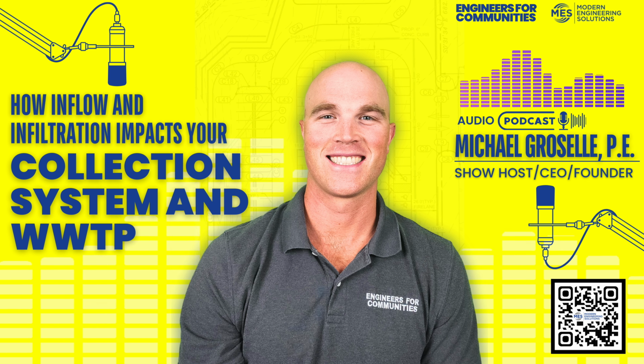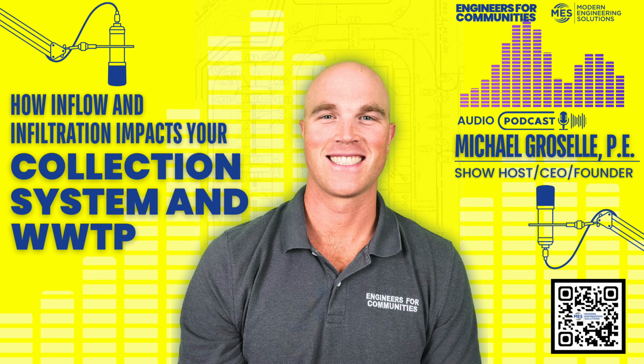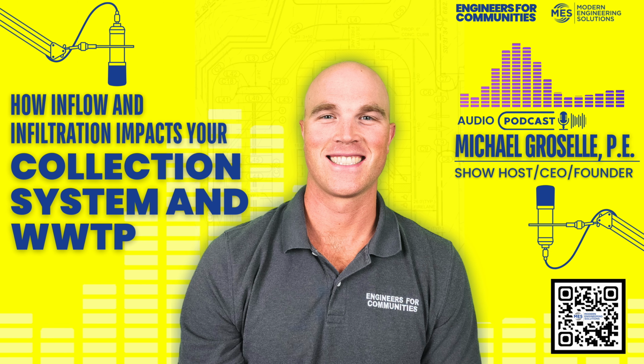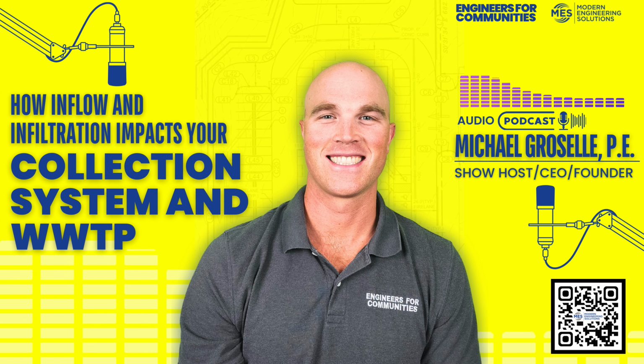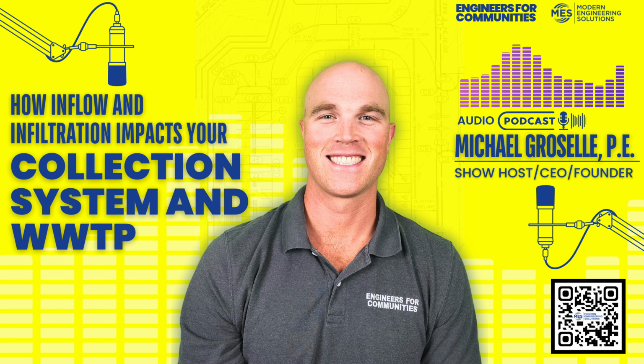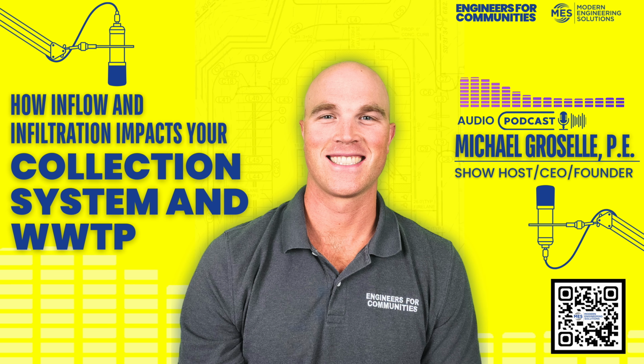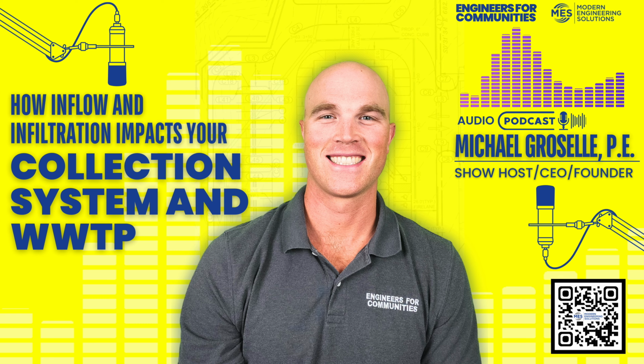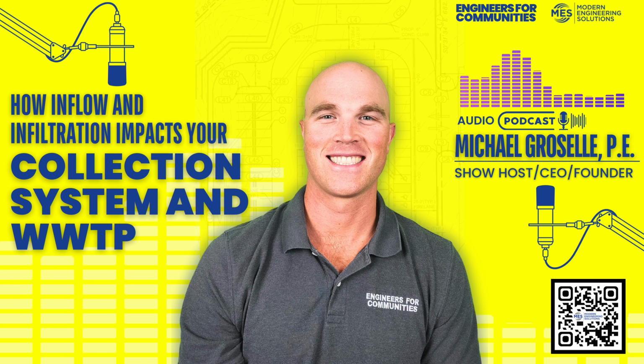This is my personal favorite, and I think this is kind of the gold standard right now. A lot of people are using this. This is pipe inspection using CCTV, that's closed circuit television inspection. So what happens is a guy sits above in a van on the ground surface, and he places a robot that has different video cameras on it, and it goes into the line. It measures the length of the line, it can tell you the slope, and it can do a visual inspection. So he's getting real-time video data of the condition of the pipe.